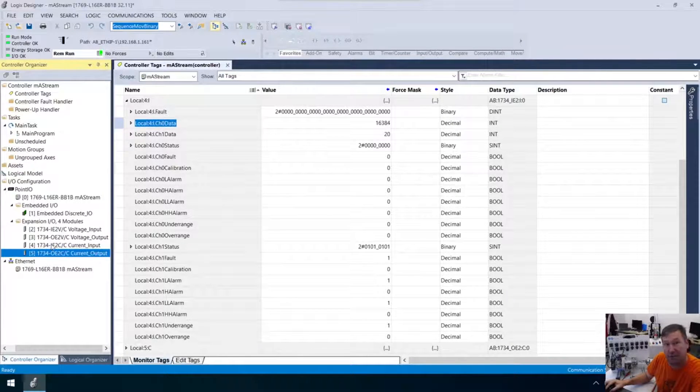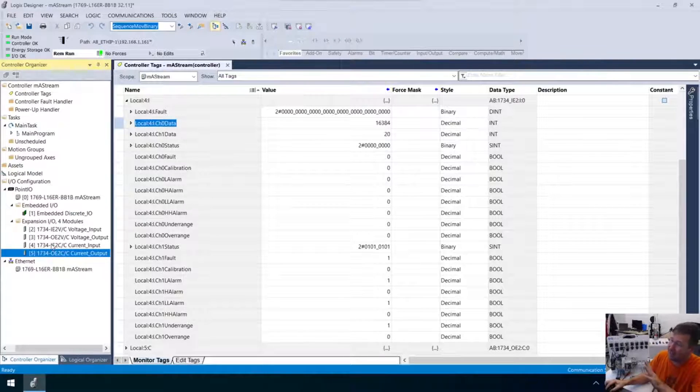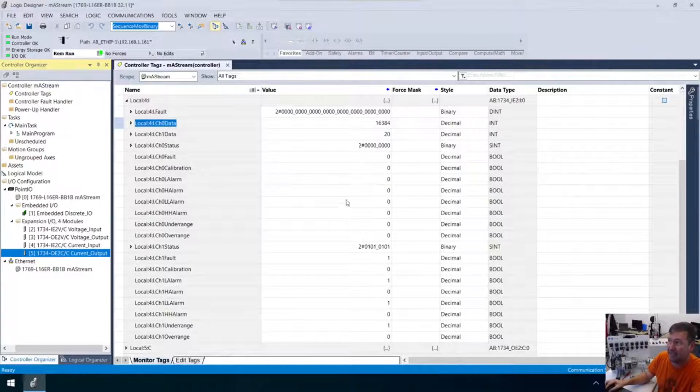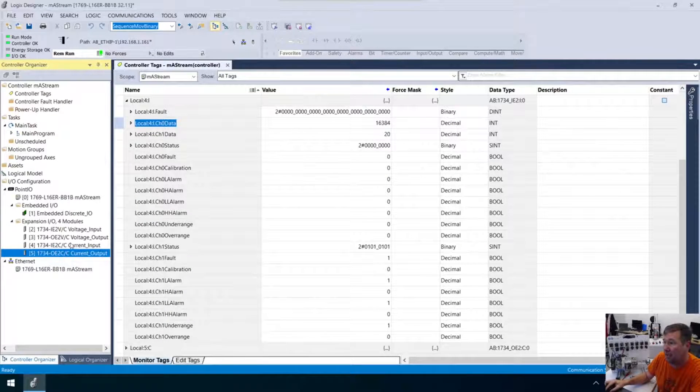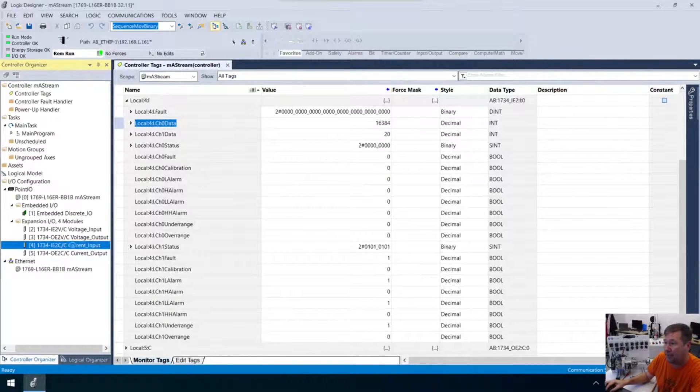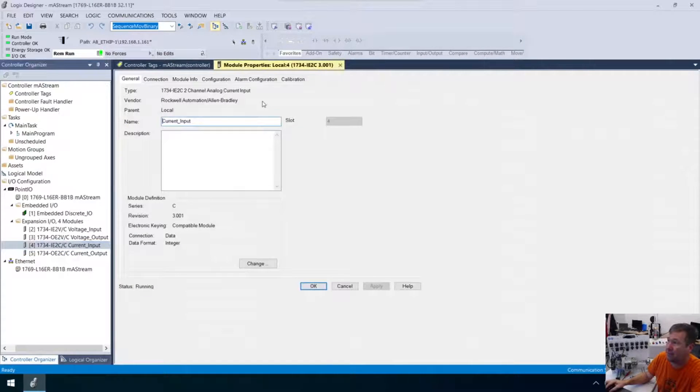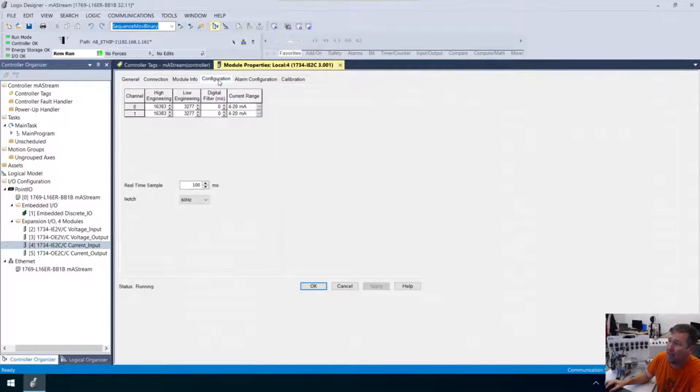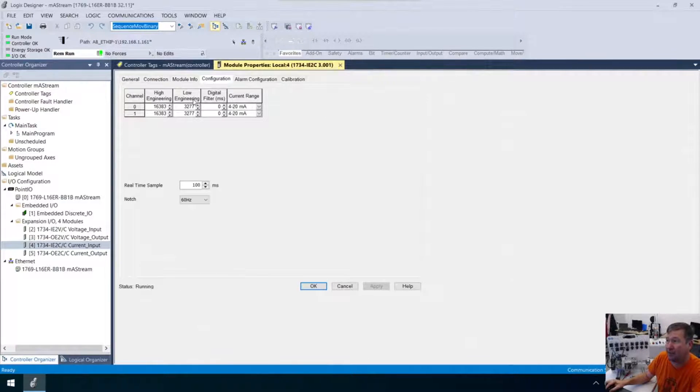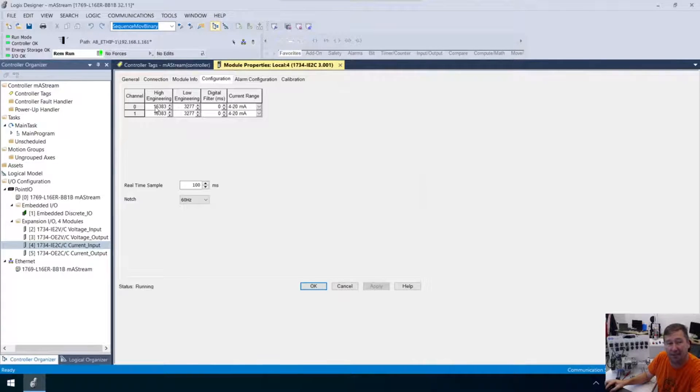But used to, it was written in many of the PLCs. This is not a knock on Rockwell. In many of them, it is a guessing match to figure out what these values are. But if we double click on this module here, it's going to bring up the module properties. And then right here, we have the configuration tab. And if we look at it, here it is. Our low engineering is 3277. And our high engineering is 16383.